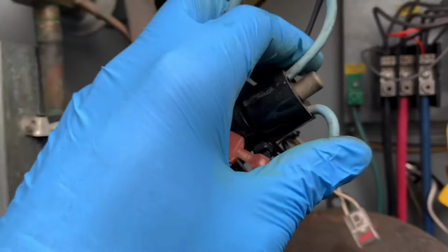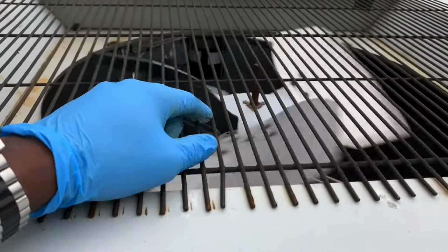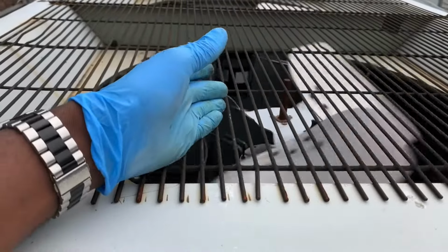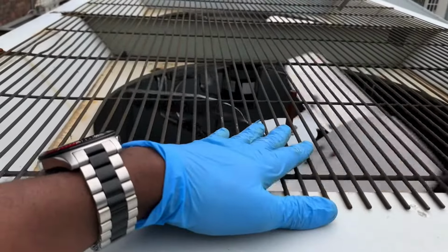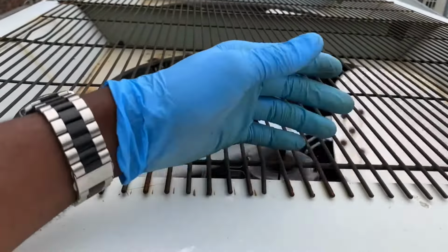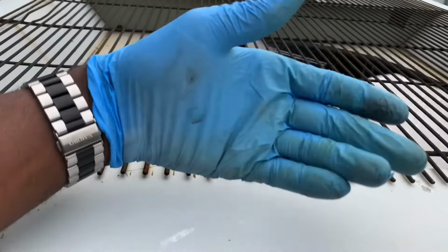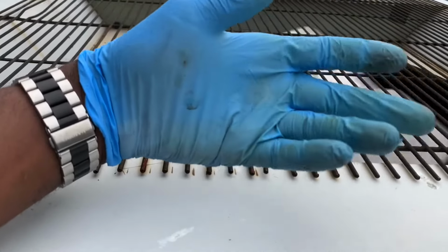And likewise, like I said earlier, on the high side, if the condensing fans up top here are not working, if the condenser coils are dirty, if the system is overcharged, or you get a bad restriction in the system, the pressure on the high side builds too high, and it's bad for the compressor. So basically the high pressure and the low pressure safety switches protect your compressor.